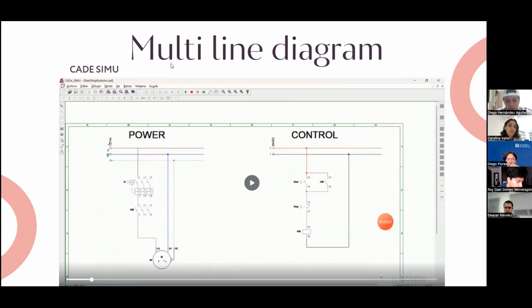In the control circuit, we have the start and stop buttons. First, we need to connect the input of the start button, which is a normally open contact, to 24 volts DC, and the output is connected to the input of the stop button, which is a normally closed contact. The output of this is connected to the coil, and the output of the coil is connected to the ground.